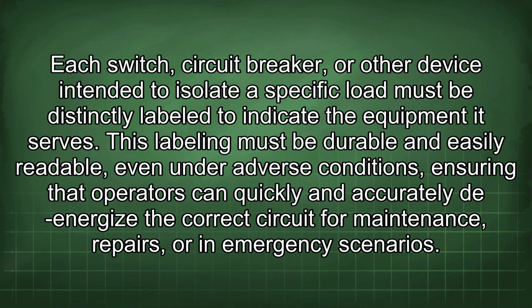Each switch, circuit breaker, or other device intended to isolate a specific load must be distinctly labeled to indicate the equipment it serves. This labeling must be durable and easily readable, even under adverse conditions, ensuring that operators can quickly and accurately de-energize the correct circuit for maintenance, repairs, or in emergency scenarios.